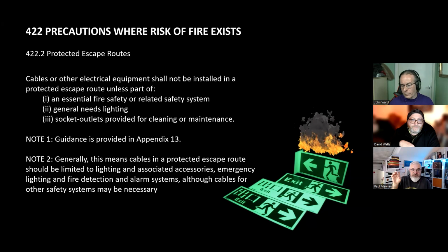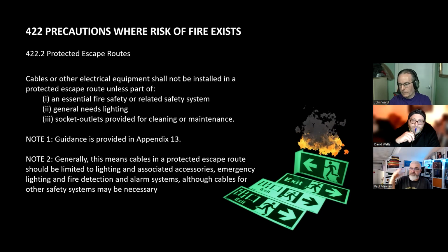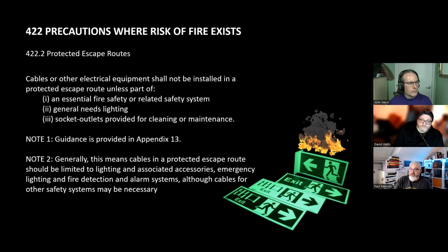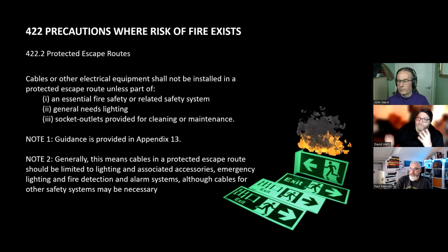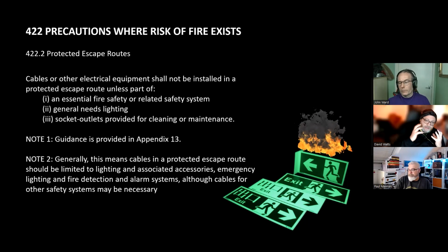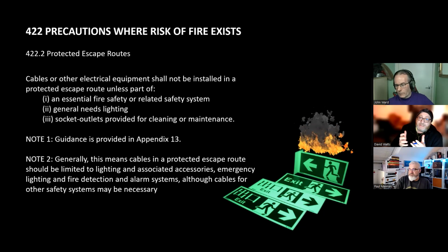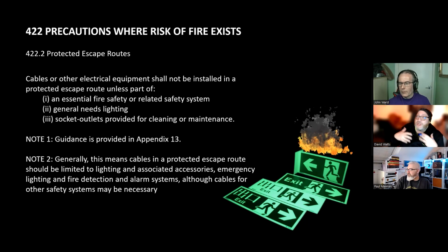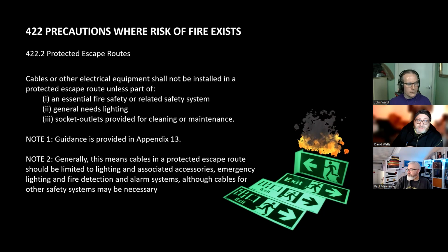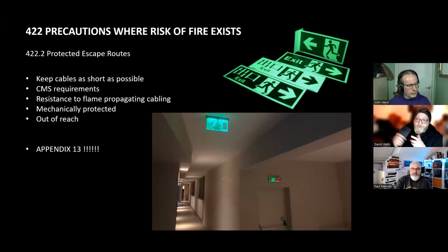There's also an additional note that says generally cables in protected escape routes should be limited to lighting and associated accessories, emergency lighting, fire detection alarms, although cables for other safety systems may be necessary. If you have, I don't know, a fire rated feeder that does fire alarm panels on each floor, or ventilation extract, you've got to be practical with this. It's definitely not like, oh, a regulation, I'll do that now. It's really about a way of thinking about the approach here. It's like an extra responsibility you've got to consider with your designer. You've got to talk with the other designers and the other planners about this. But you can't just throw any system in.